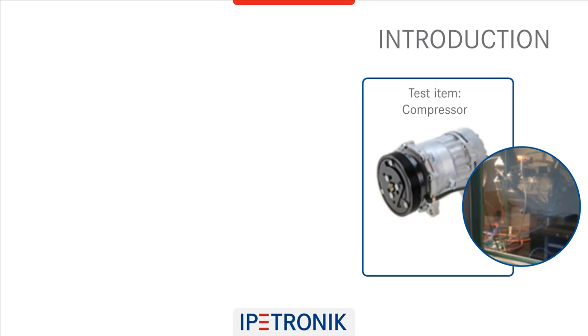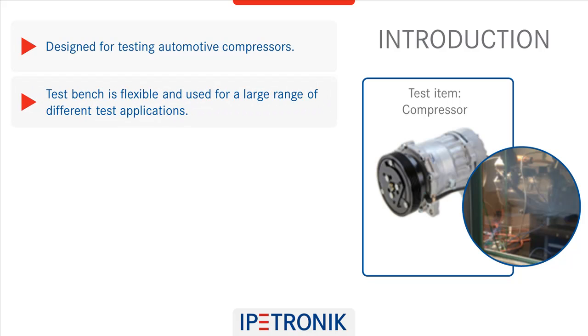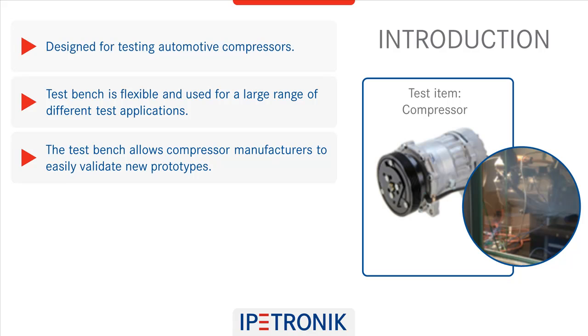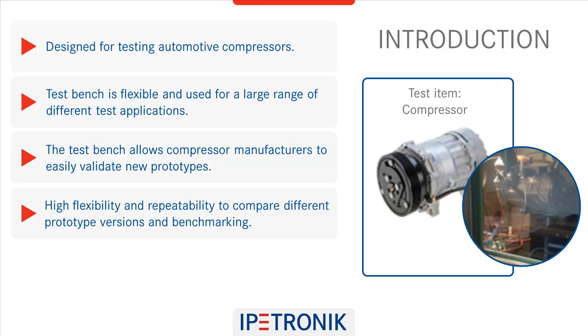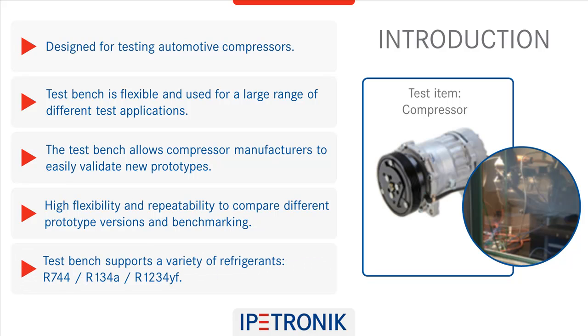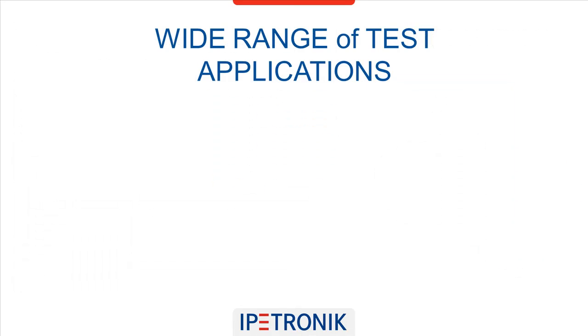The IPE test bench is designed to test compressors for automotive applications. It has been designed to be very flexible in order to adapt to a variety of test applications which are compliant with VDA standards. The IPE compressor test bench allows manufacturers to easily validate their products. The system's flexibility covers different test setups and guarantees high repeatability for the comparison of prototypes and for benchmarking purposes. Pipework and overall system design supports a variety of refrigerants, including high-pressure CO2.